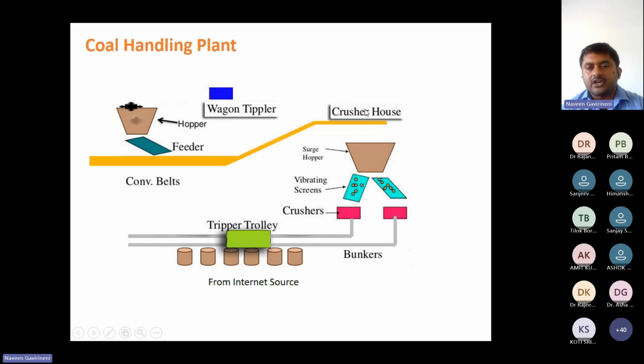Now this is the crusher house, as I have explained. So there is a crusher arrangement and after that there is a screen arrangement. This is the vibrating screen. The purpose of the vibrating screen is to remove the oversize and undersize coal, because in CFBC we need the 6 coal size. If more than that coal size goes to the boiler, what happens? There is a chance of increased retention time, and that will result in LOI, loss on ignition. Loss on ignition is nothing but wasting the coal. So for that purpose, this is the vibrating screen application.